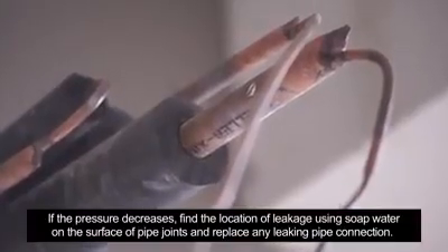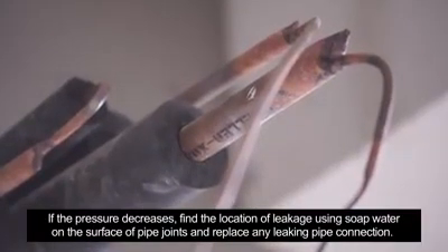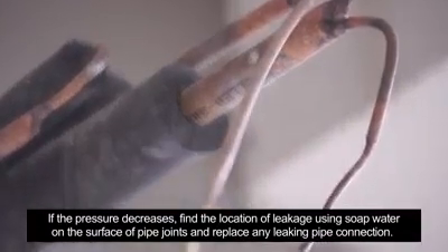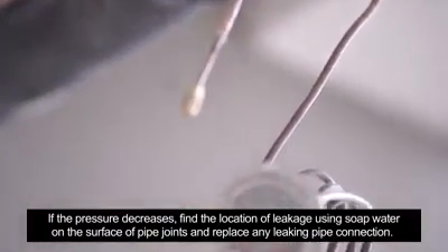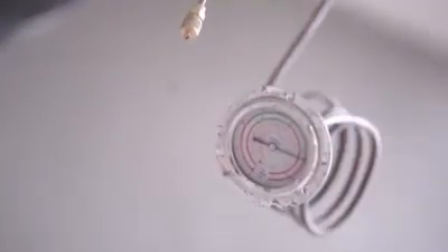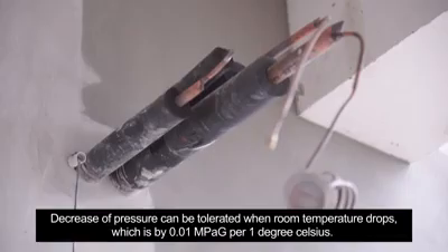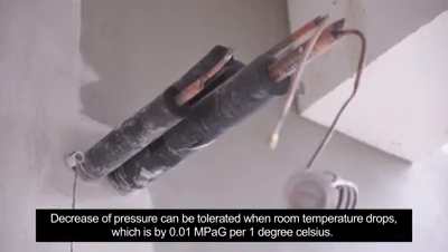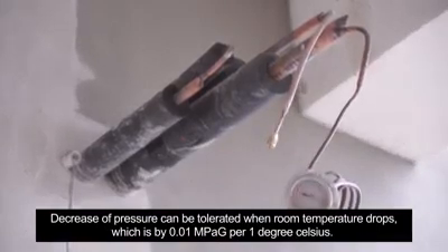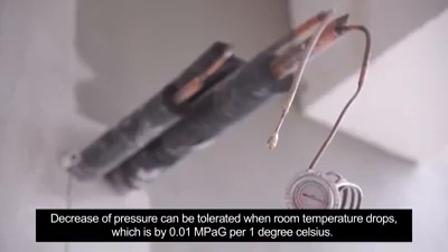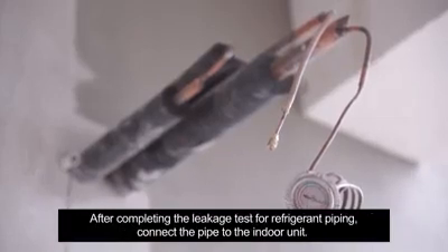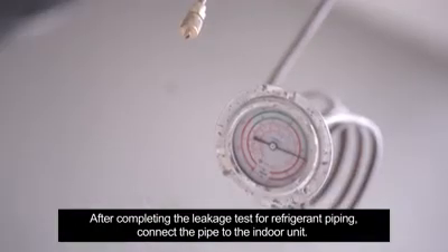If the pressure decreases, find the location of leakage using soap water on the surface of pipe joints and replace any leaking pipe connection. Decrease of pressure can be tolerated when room temperature drops, which is by 0.01 megapascal per 1 degree Celsius. After completing the leakage test for refrigerant piping, connect the pipe to the indoor unit.